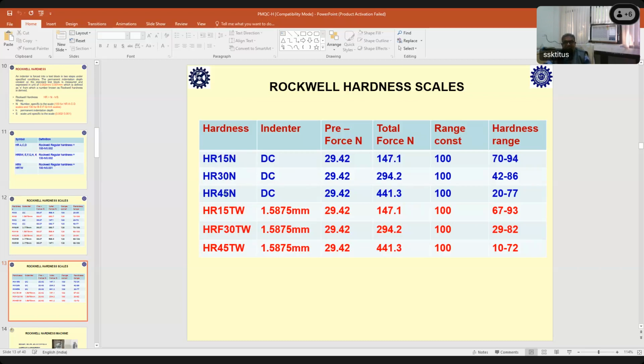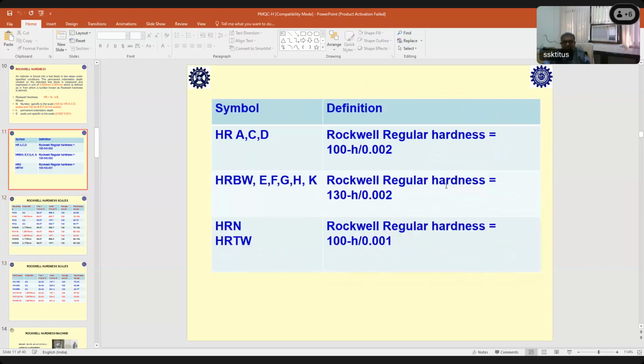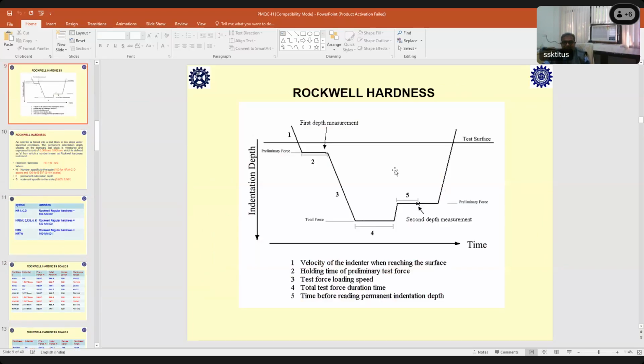And in the HR 45 scale it is 45 kg. Because this is a very small force, the penetration depth will be small, and there are some very soft metals for which it is used. Similarly, we can use the ball indenter for the same forces, 15 kg, 30 kg and 45 kg. This scale is also part of the Rockwell scale, and we call these superficial scales. Now, this is the timing cycle I was talking about.